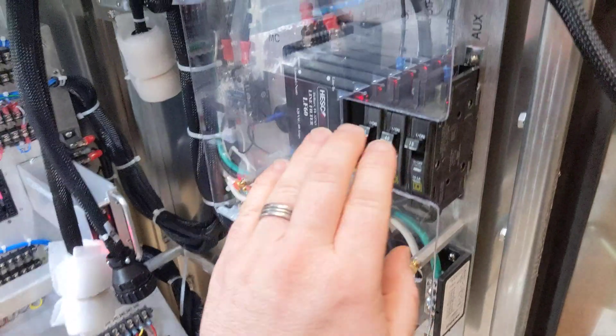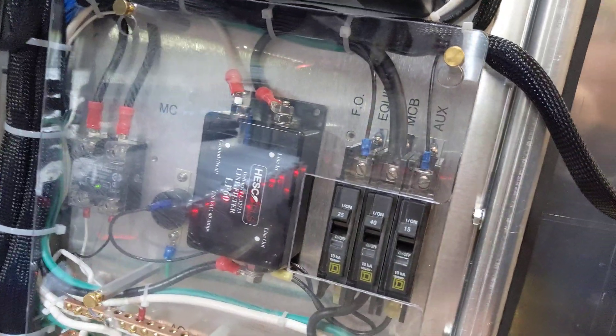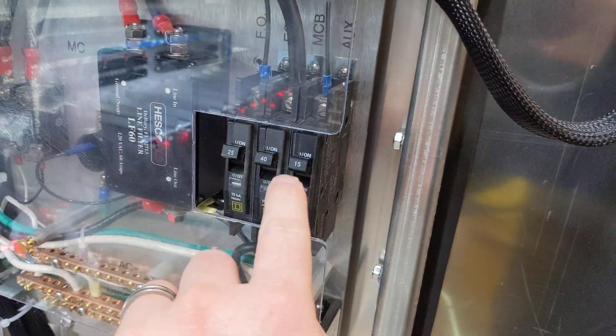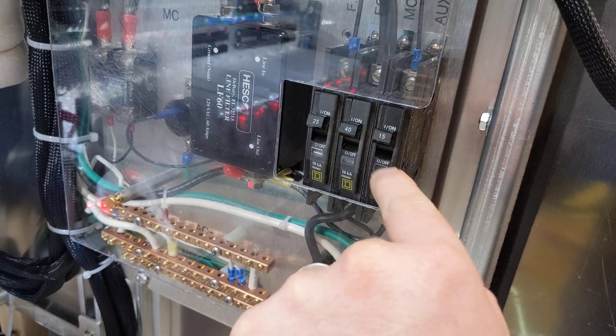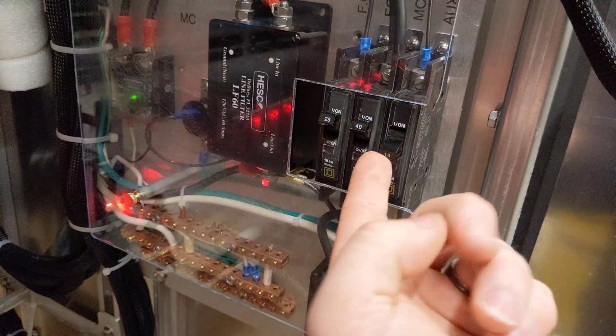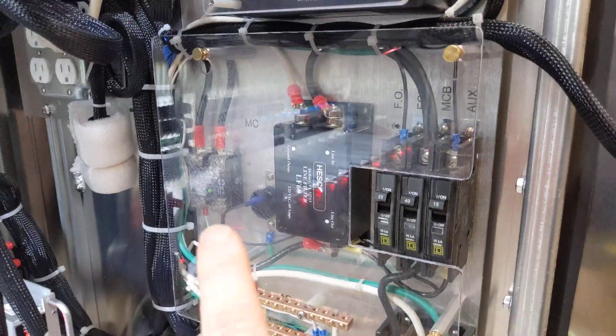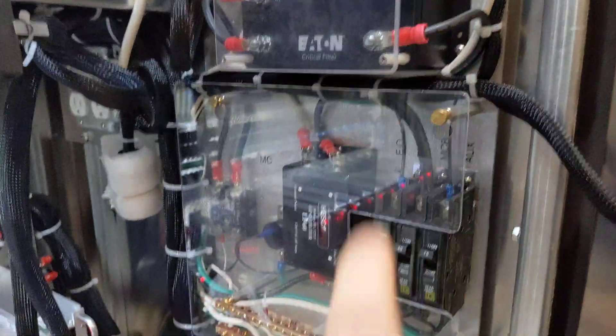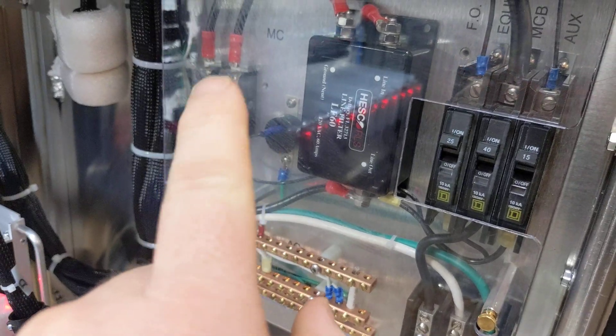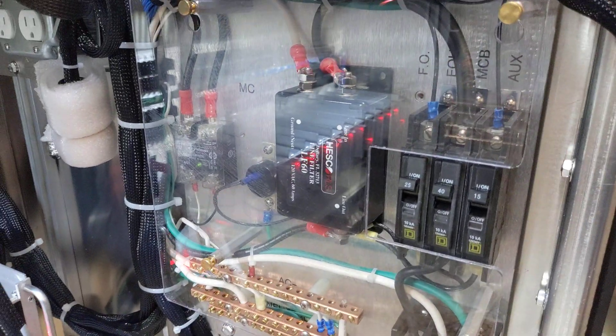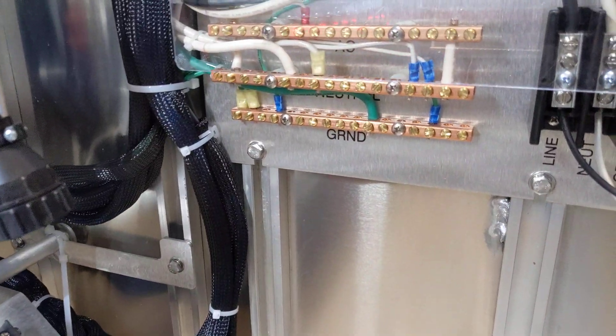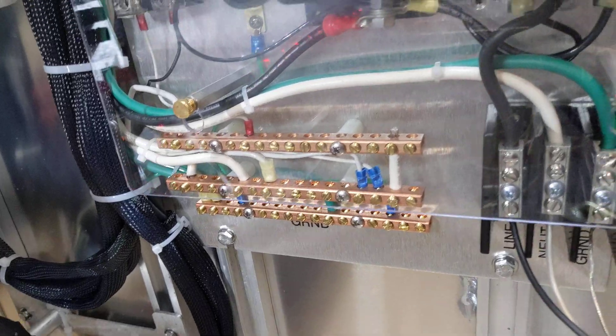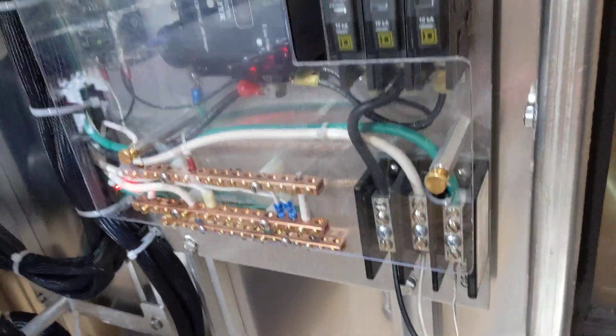We have some breakers here that are connected to several different circuits in the cabinet, including the equipment, the master control breaker, and then this is auxiliary power. I would venture to say that the lighting is attached to this one. We have some surge and line protection devices in line here, as well as the solid-state relay. This replaced the mercury contactor switch, which is in older signal cabinets. And then down here, you have a few ground buses, including a neutral bus that is just tied directly to the service neutral.